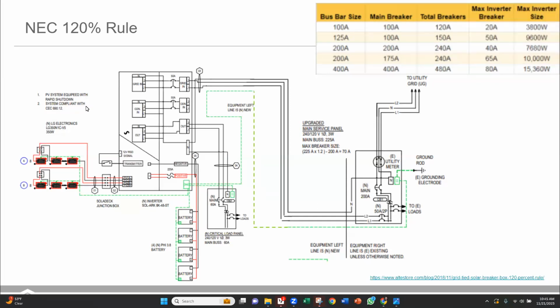Daniel, could you talk us through the 120% rule? This relates to how much power you are allowed to feed from your solar array, whether AC or DC coupled, into your main loads panel. Keep in mind that utility power typically runs through a main breaker. Let's suppose you're pulling close to 200 amps through that main breaker. You can have power flowing through it while also contributing power from a solar system. Exactly. In that case, you could overrun the bus bars.